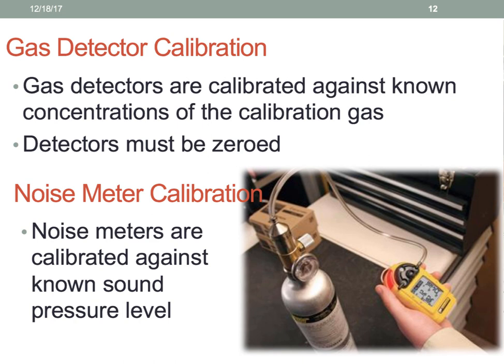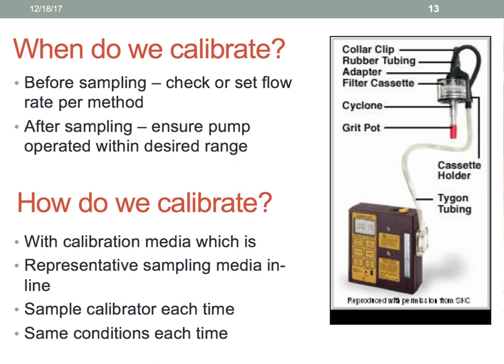So when do we calibrate? We calibrate before we sample to check or set the flow rate to make sure we're pulling air at the appropriate volume. Then after we sample, we don't touch our pump — we just check the flow rate to see if there's a significant difference or not. We calibrate after our pump has been warmed up, with a representative sampling media in line, exactly as we're going to sample. We try to do our pre and post calibrations at about the same sampling conditions.